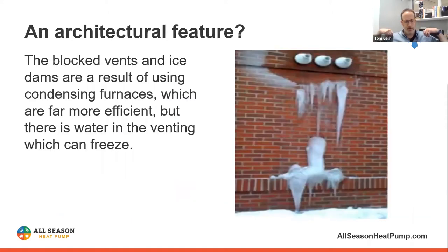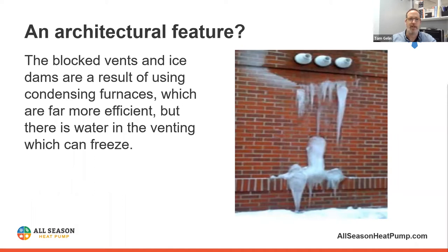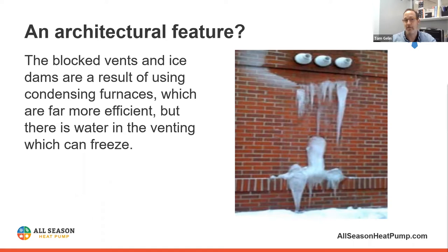Another issue many developers and builders run into: when we specify higher-efficiency furnaces, we are condensing in the vent on the way out. That water can either run down the building and look like an ice dam, or it can actually plug up the termination. Builders have called me up asking what to do about this — it's an issue. With heat pumps, those terminations are gone, and the potential maintenance issue — which can require a crane — can be eliminated.